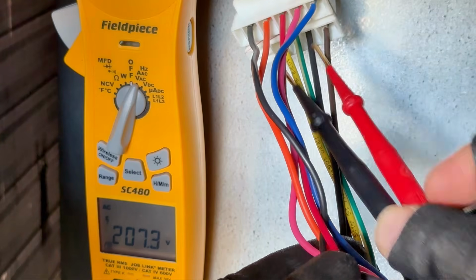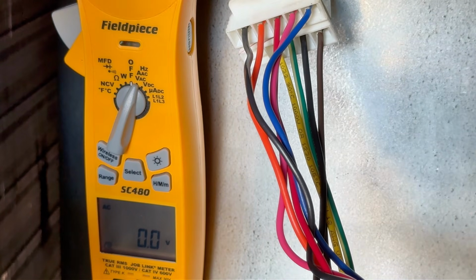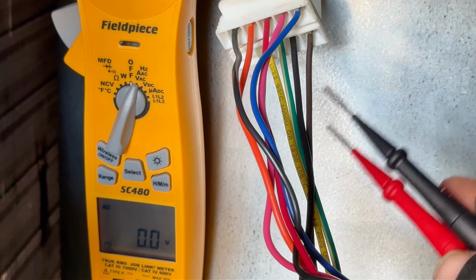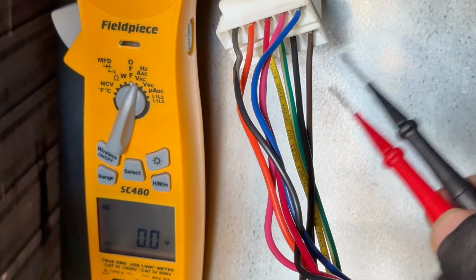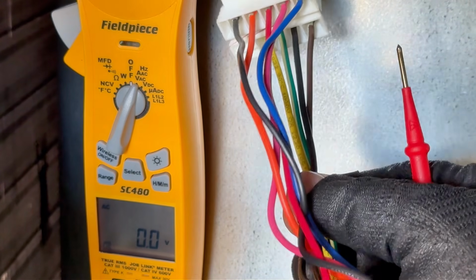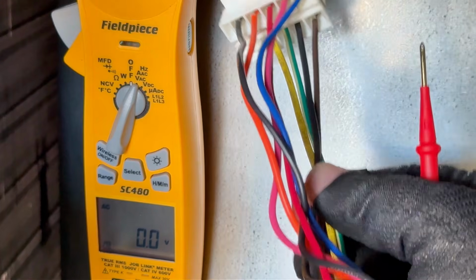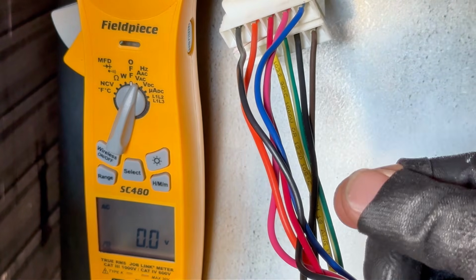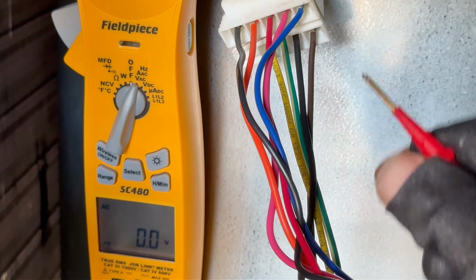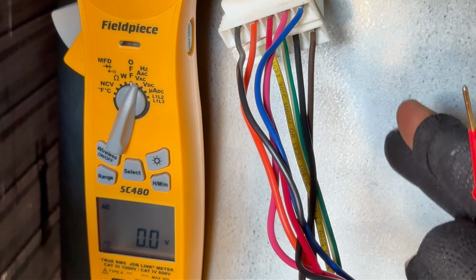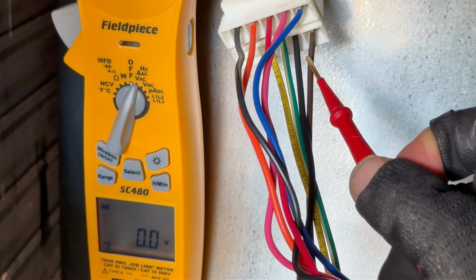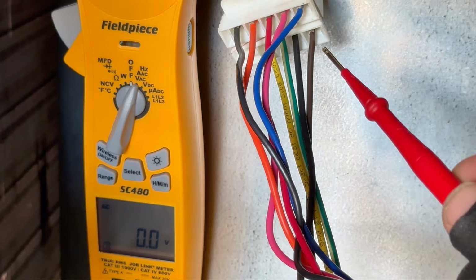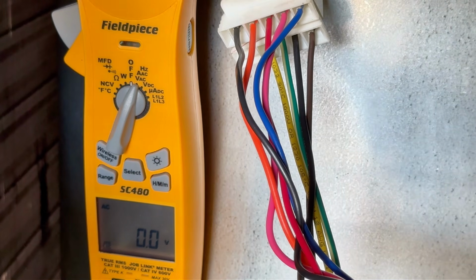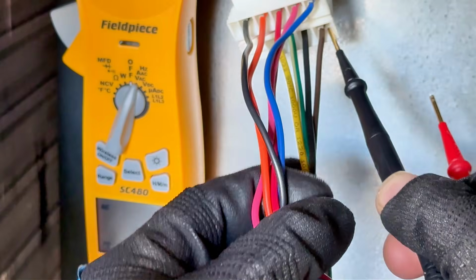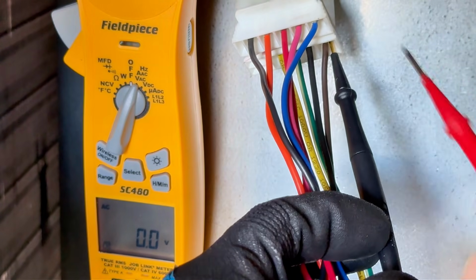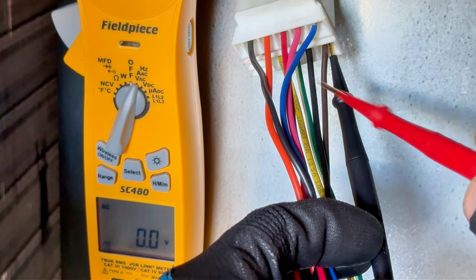208. So keep in mind with an ECM, even when you're not calling for cooling, that high voltage will always be there. Do not disconnect it with power being present there. With power here, do not disconnect it and connect it to check voltage and then connect it back. You will mess up the ECM motor. So in this one, you can just check to the back, and sure enough, we got 208. For my low voltage, I'm gonna go ahead and check common because we just said the brown is common, and we just said it's sending 24 volts on the black one.